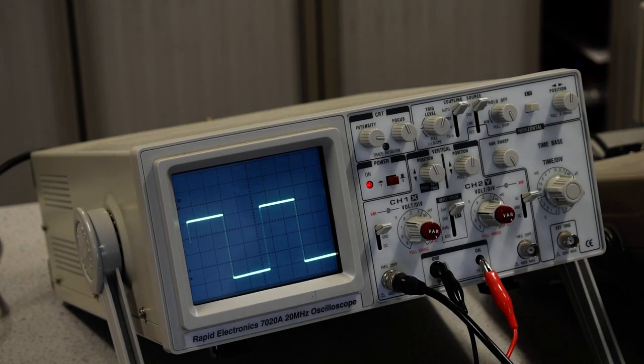So what we want to do now is see on the screen if that is, with the current settings on the volts per division and the VAR calibration setting, whether that's accurately showing 2 volts peak-to-peak.